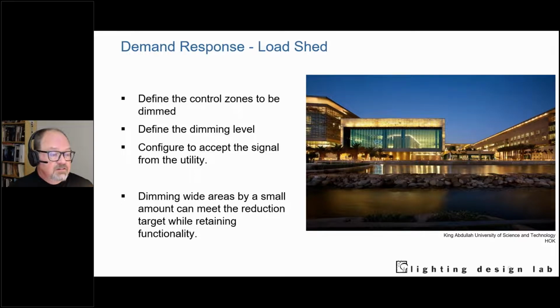We talked about this the other day. Load shed demand response is basically the idea that on a large area, if you dim the lighting down by a certain amount, when the electric utility is either going to be having a potential brownout, for example, if there's not enough power, or if we want to save a little bit of energy from a time of day standpoint.